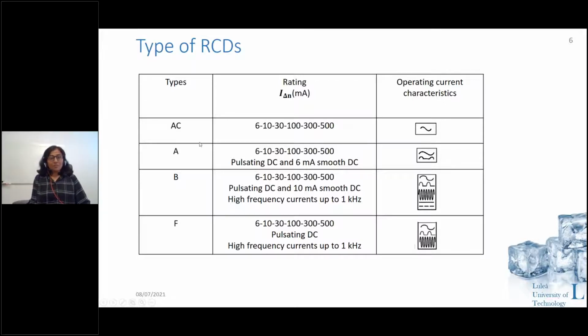Type A RCD is used for pure AC as well as pulsating DC, and it can also take up to 6 milliampere of smooth DC. Type B RCD, which is one of the most important RCDs we should be using these days, is used for AC, pure DC, pulsating DC, and even high frequency currents up to 1 kilohertz.